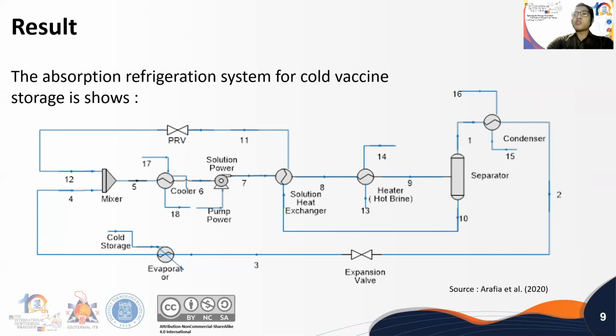In the evaporator, the cold refrigerant in flow 3 will absorb the heat from the vaccine. So the refrigerant will evaporate in flow 4. The refrigerant from evaporator in flow 4 will mix with the absorbent in flow 12. The liquid content at the bottom of the separator contains a small amount of ammonia, because most of the ammonia goes to the top of the separator, so that the bottom liquid is called a weak solution in flow 10.